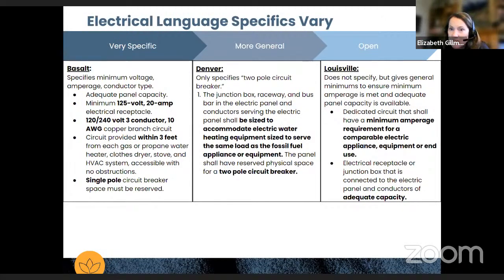Whatever we choose needs to be flexible. From a heating standpoint, it's almost certainly going to have to be 2-pole something. Definitely a single 125 volt 20 amp breaker is not going to suffice for any sort of heat pump system. The electric capacity is a really tricky thing to nail down, because we're guessing on equipment to replace that furnace in 20 years, and again, it doesn't exist. So we don't know if we'll be able to purchase a heat pump that works better than our heat pumps today.